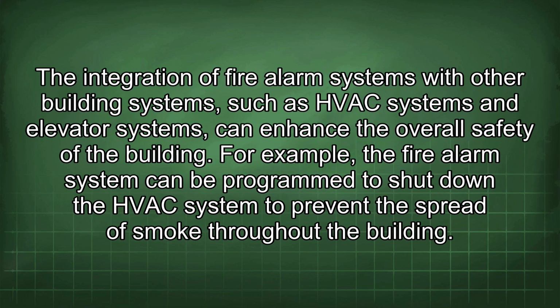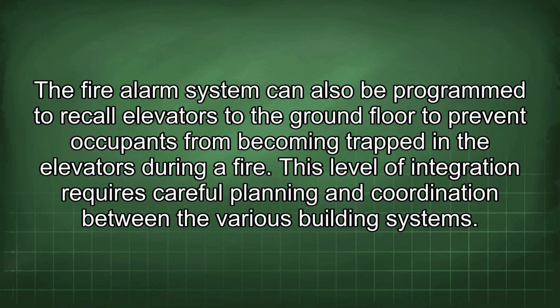The integration of fire alarm systems with other building systems, such as HVAC systems and elevator systems, can enhance the overall safety of the building. For example, the fire alarm system can be programmed to shut down the HVAC system to prevent the spread of smoke throughout the building. The fire alarm system can also be programmed to recall elevators to the ground floor to prevent occupants from becoming trapped in the elevators during a fire. This level of integration requires careful planning and coordination between the various building systems.